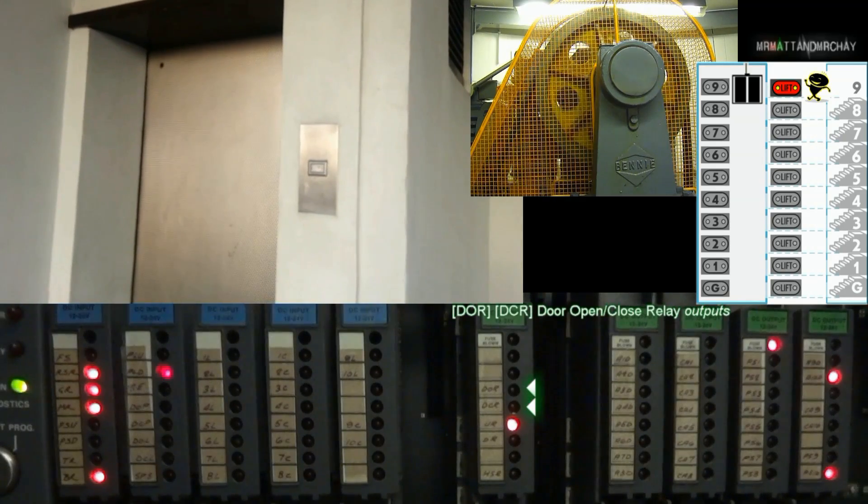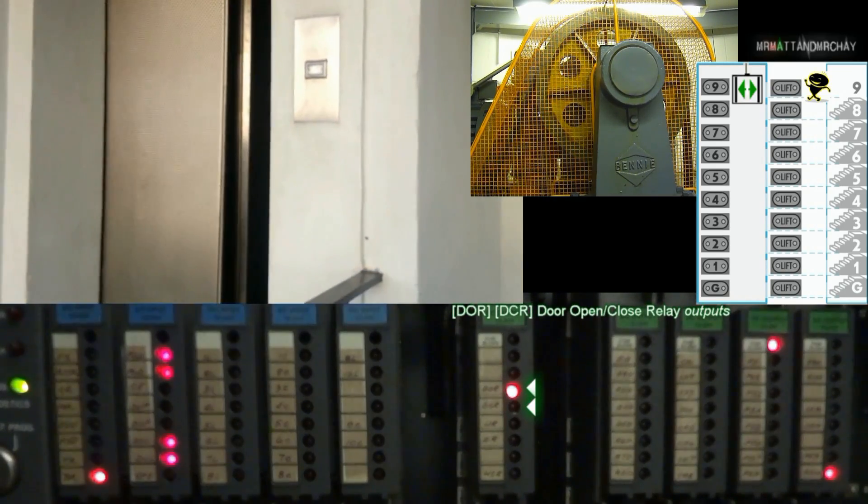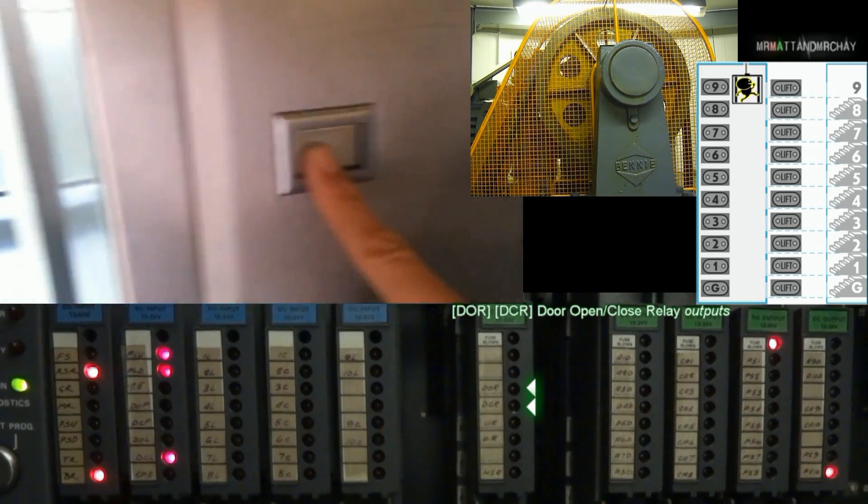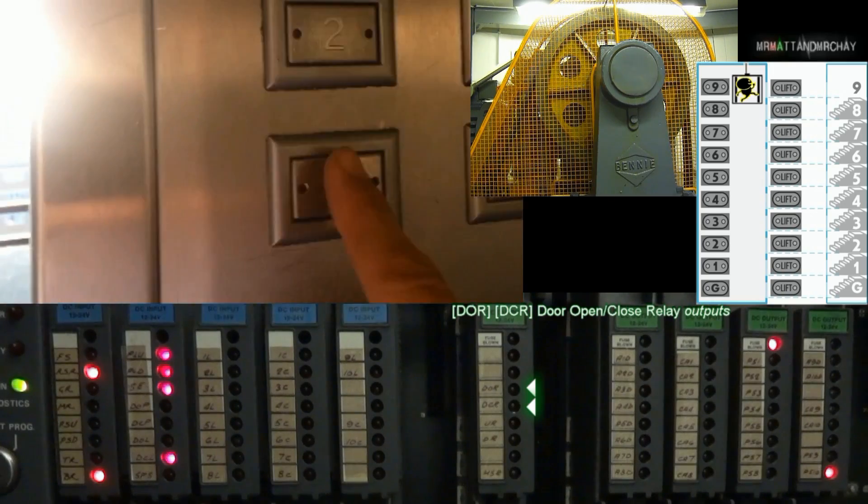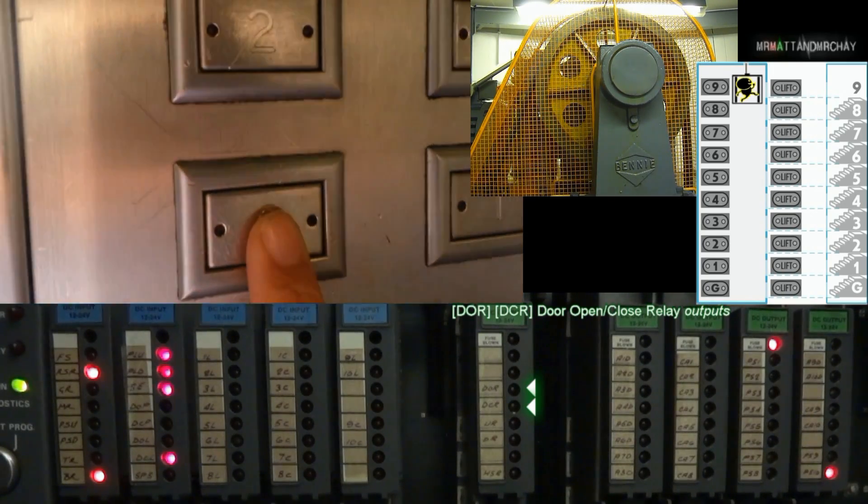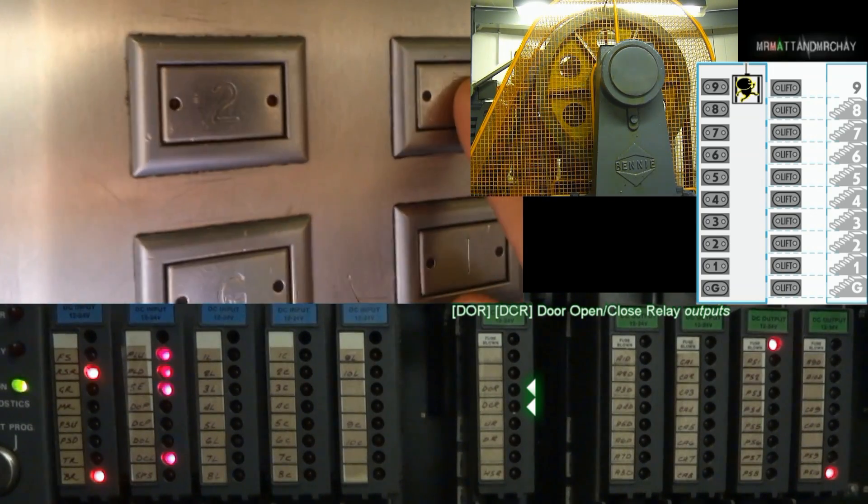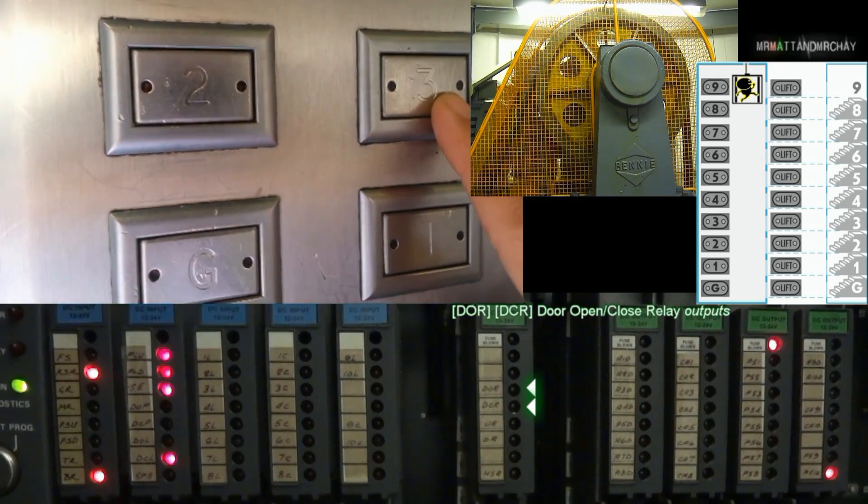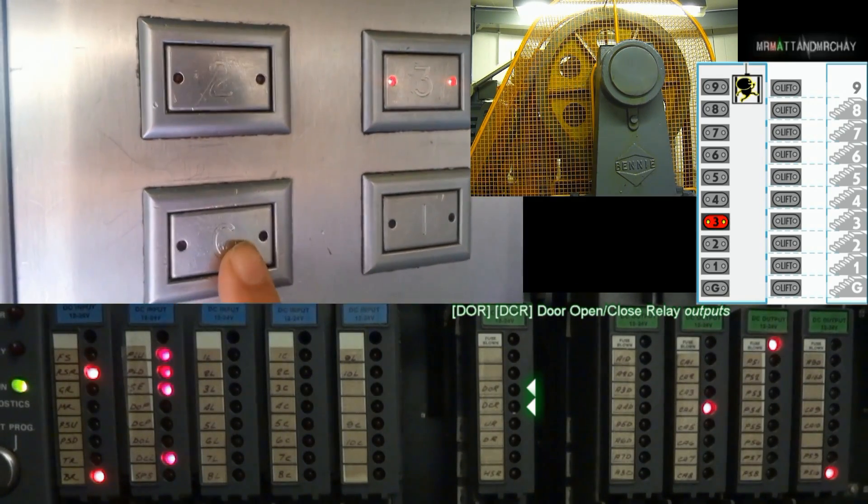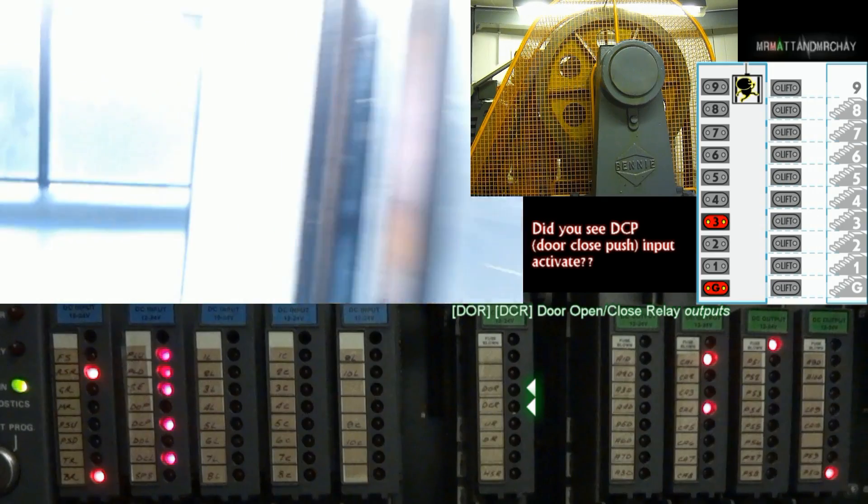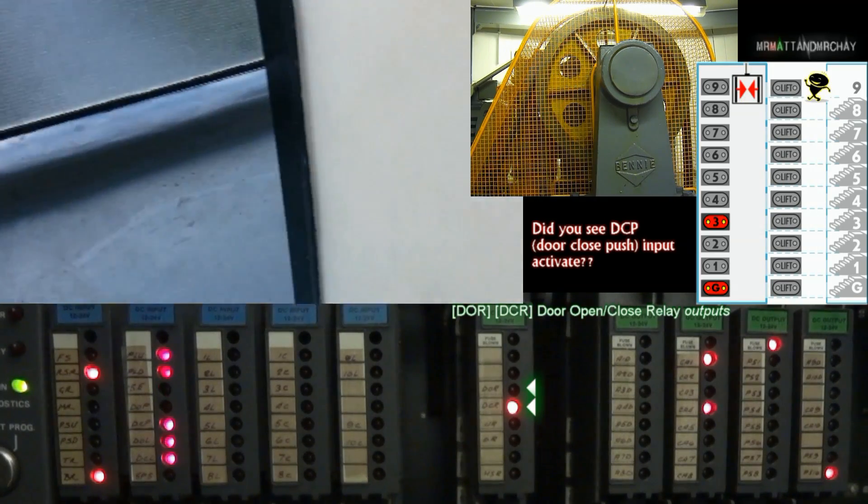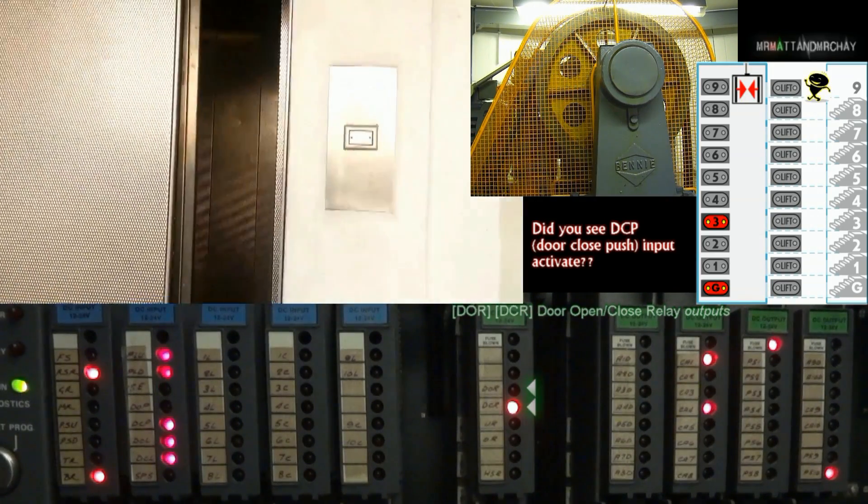DOR, door open relay. This opens the lift doors. And DCR, door close relay, closes the lift doors. These outputs alone are not powerful enough to operate the door motors directly. Instead, they connect to bigger relays in the cabinet that switch the higher voltage to the doors.